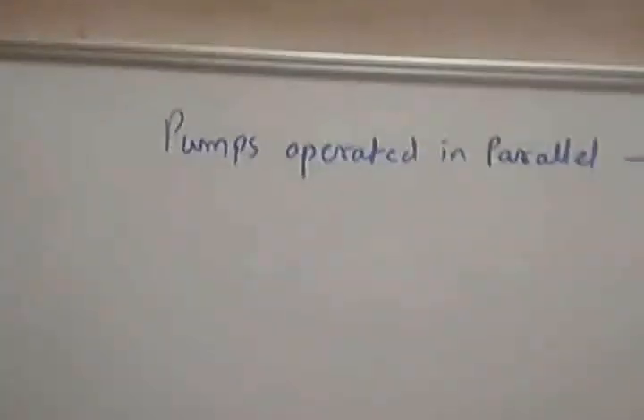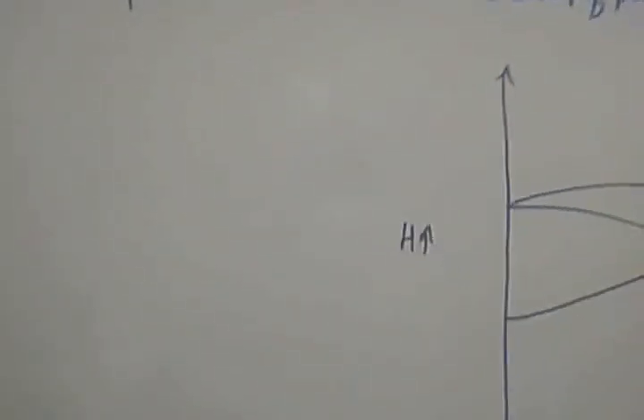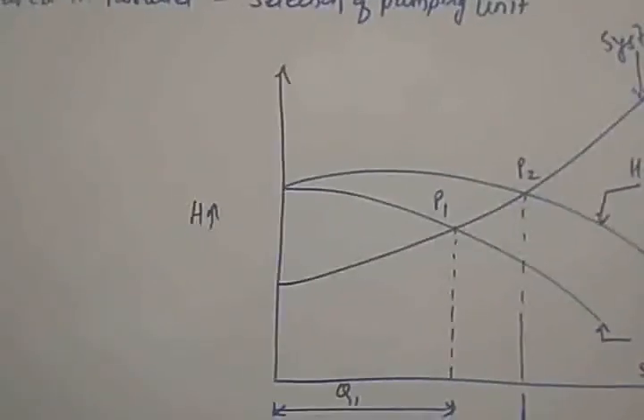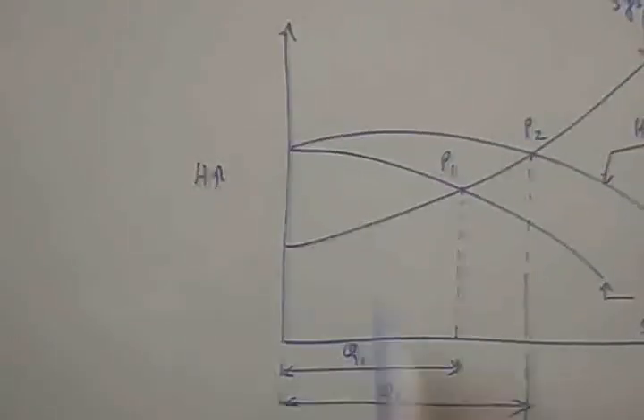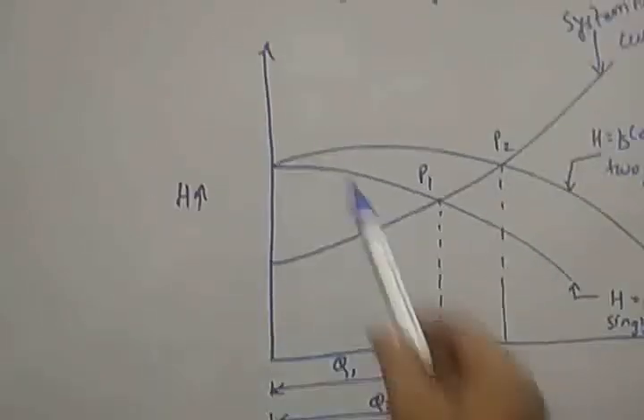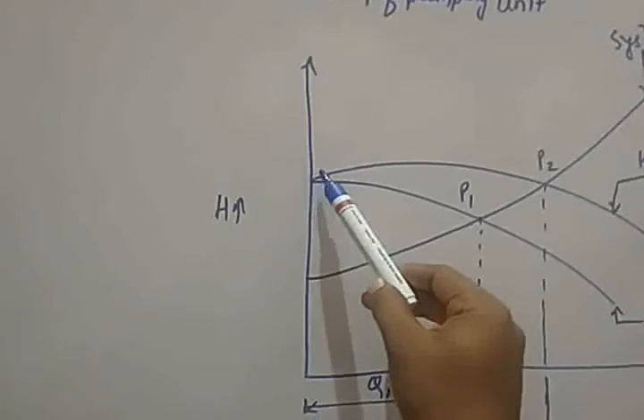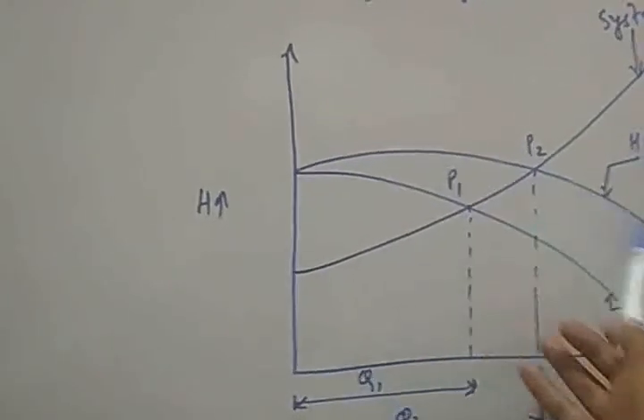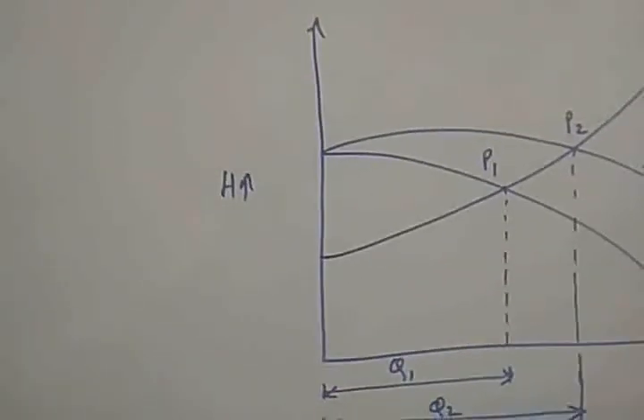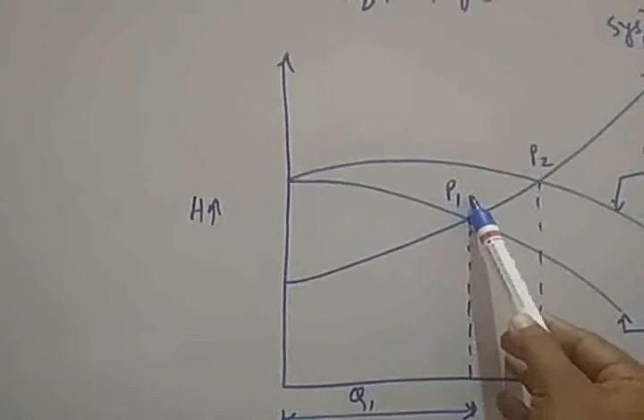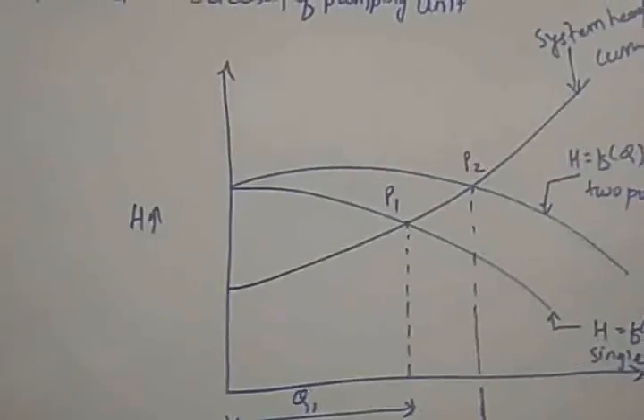Now we will see the selection of a pumping unit when the pumps are in parallel. As with pumps in series, we will be plotting the system head curve, then the H versus Q plot for a single pump, and also the H versus Q plot for the sum of discharges of two pumps versus head. Then we can see the point of intersection for a single pump and the point of intersection for two pumps.